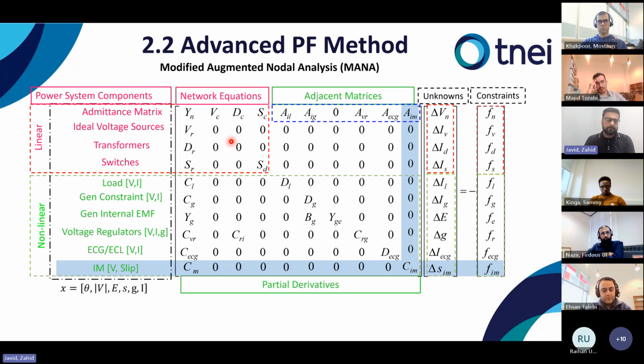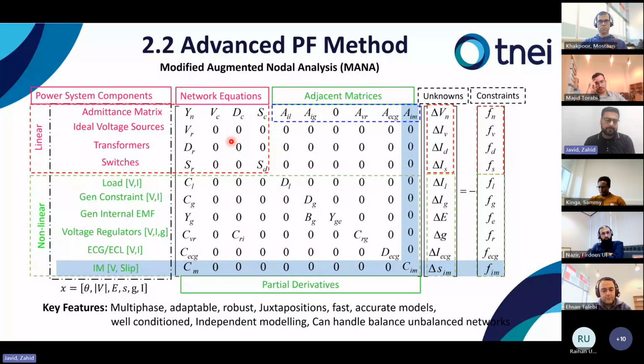For the state variables, it can be theta, the angle, the magnitude of the voltage, internal EMF of the generator, slip of the induction machine, tap positions, and current of the IBRs. The key feature is the multi-phase formulation. It's adaptable, robust, and we can juxtapose the different components side by side in the formulation. And it is fast and accurate. Components are modeled with their terminal voltage and current, which are hard to model in the Y bus, so they are more accurate models with the constraints. The matrix is well conditioned. I will explain later in the results how it is well conditioned compared to the classical nodal analysis method. Each component is modeled independently, so they are not dependent on each other. So it can be extended with different models easily, and it can handle both balanced and unbalanced networks.